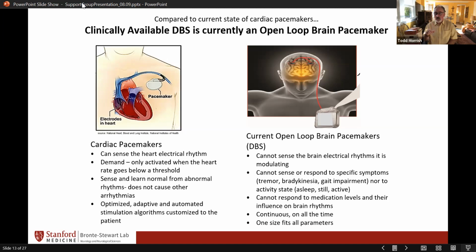Whereas in the closed loop model that you're proposing, there is data being generated in the probe, or whatever you call the unit that's implanted in the brain, back down to the stimulator. And so that's the closed loop. Exactly. Understand that correct? That's perfect. The open loop essentially is steady state. So it's not going to change unless a clinician changes it or unless a patient changes it on their patient programmer. Whereas you're right, closed loop would adapt and change either to a neural signal coming from the DBS lead or from kinematic signals coming from ankle sensors, for example.